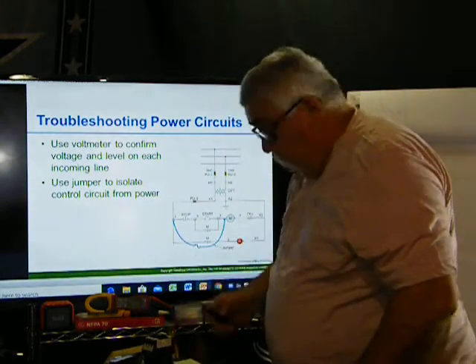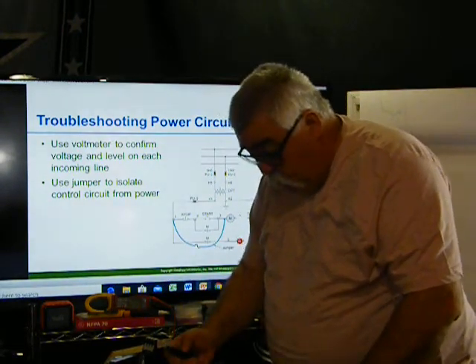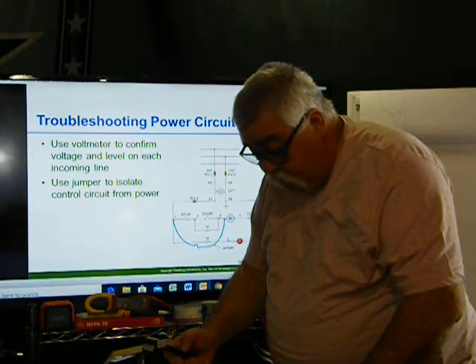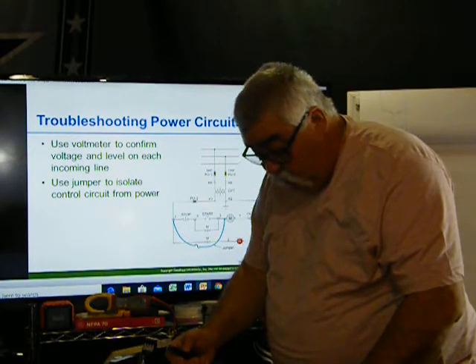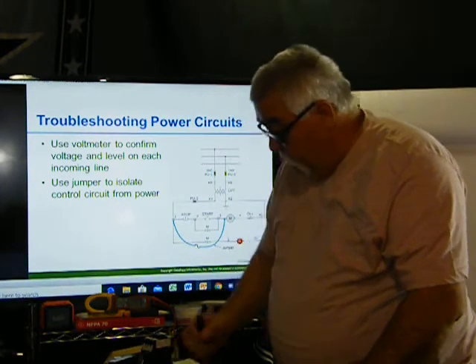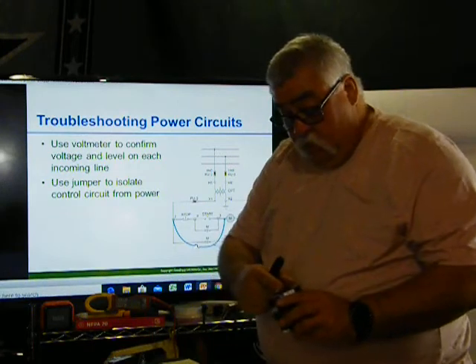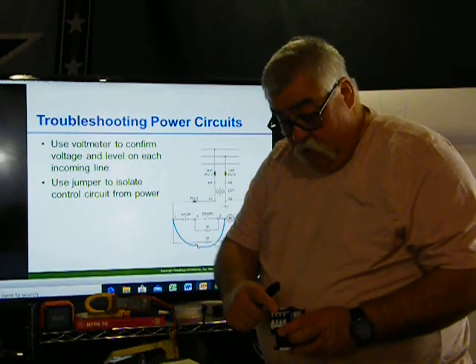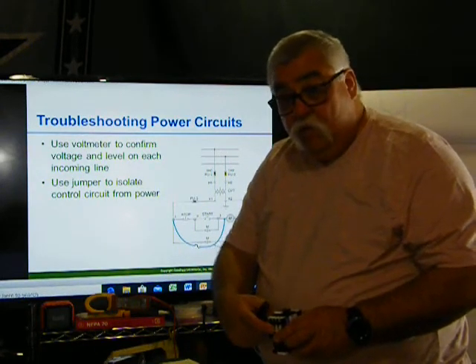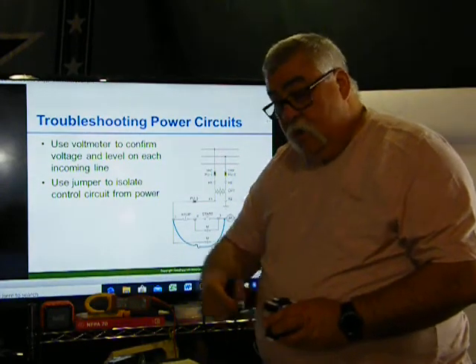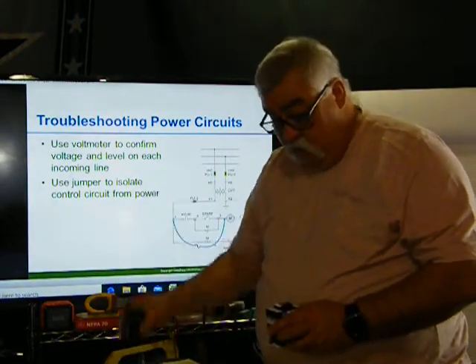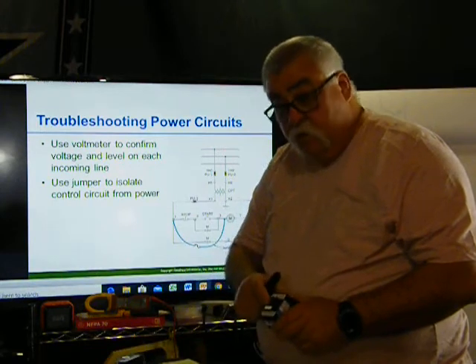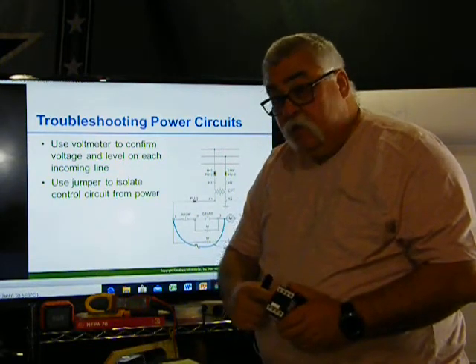Obviously this is from figure 18.2, where a manual motor starter, use a screwdriver to close the contacts. Once the contacts are closed, check to verify that the voltage is at T1, T2, T3. So if you close this, and here's T1, T2, and T3, if you've got voltage at the bottom, then the problem is with either the motor or your relays. Okay, so voltage comes across here. The other thing is the contacts on this.